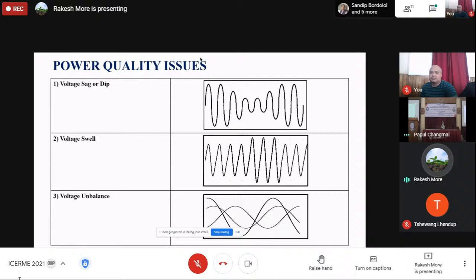Voltage swell. As per the IEEE standard, a voltage swell means an increase in the voltage level to between 110% and 180% of the normal system voltage. The voltage swell phenomenon in the system occurs due to switching of a large inductive load at a time or energizing of a large capacitor bank. So as we energize the capacitor bank at a time, it raises the system voltage level.